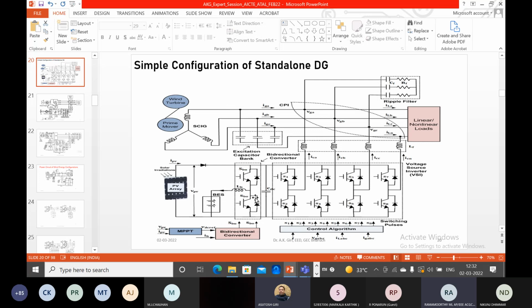That's why I told you, in standalone mode operation, the mismatch will always be there, a possibility we cannot deny. The mismatch between the load and generator will always be there, and the mismatch of the real power will be stored in this battery. That's why a bidirectional converter is also used. Sometimes the battery will be in charging mode, sometimes in discharging mode. Another possibility is when both sources are ineffective for some reason. Suppose a 5 kilowatt installed capacity is generating only 1.5 kilowatt, and a 2 kilowatt installed capacity is generating 0.5 kilowatt, then you must have this backup, and a proper calculation of this backup.